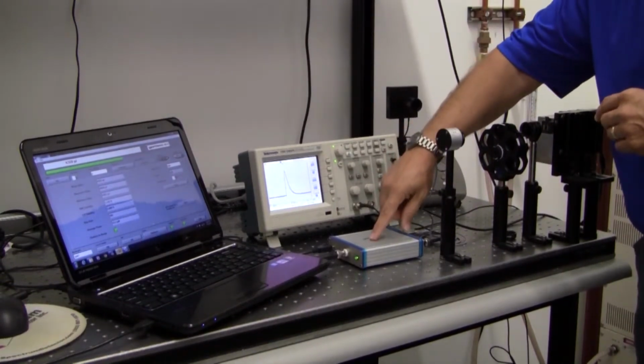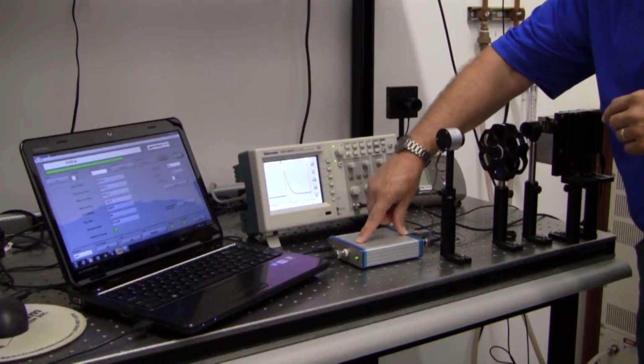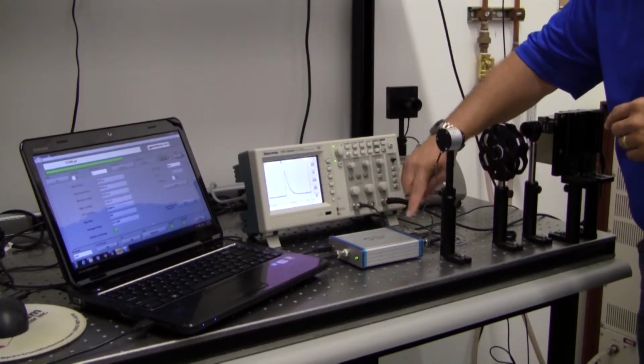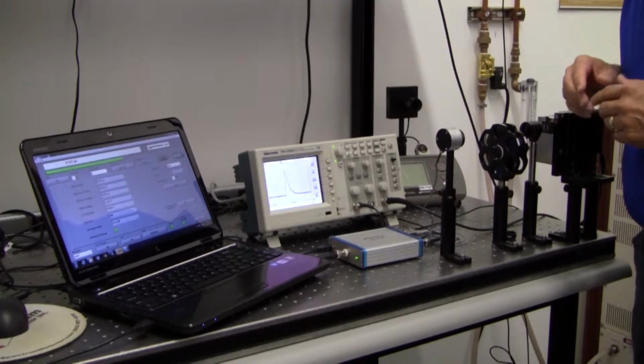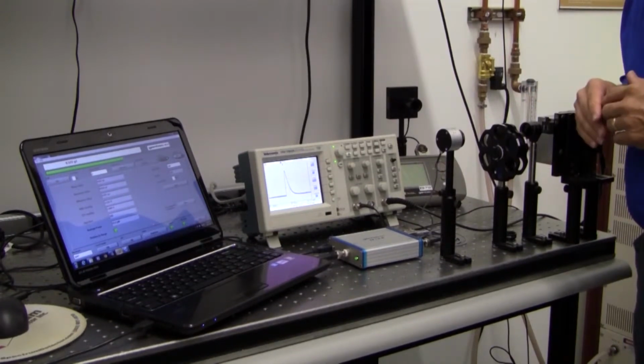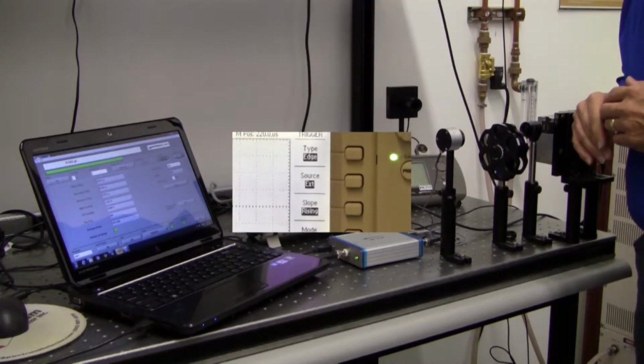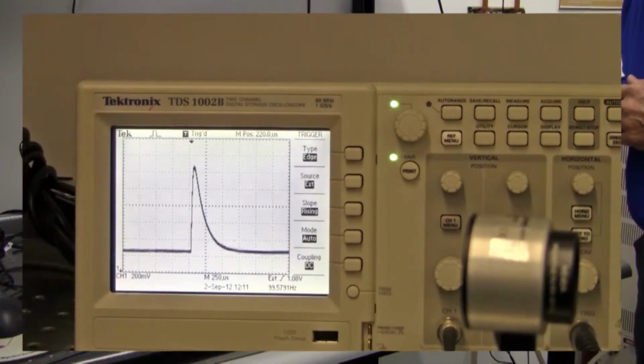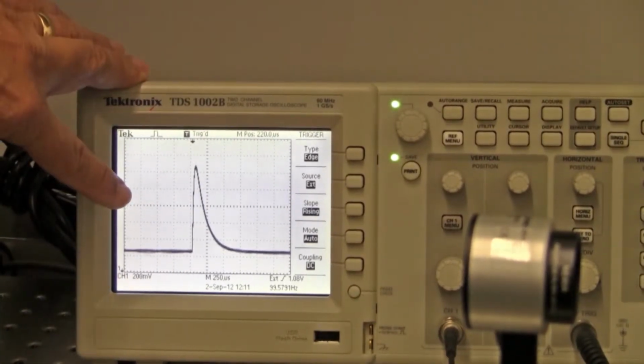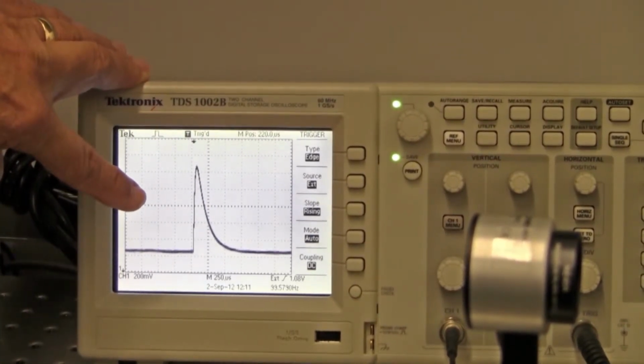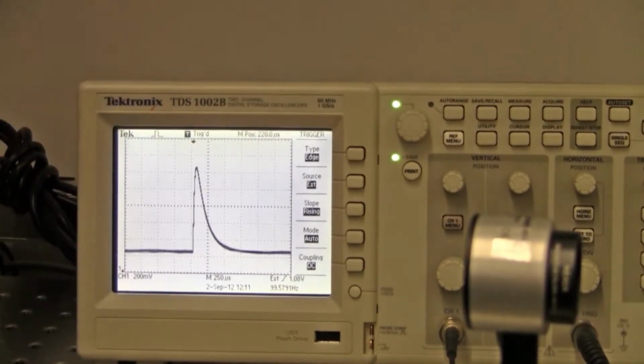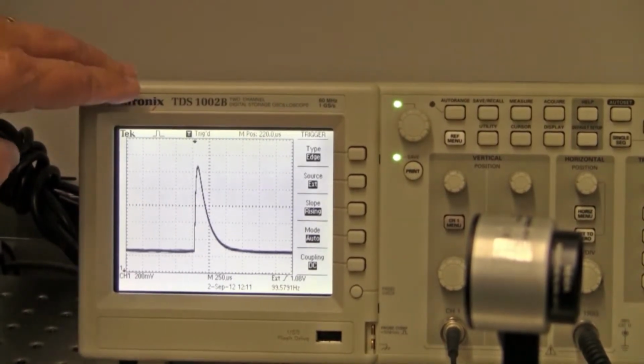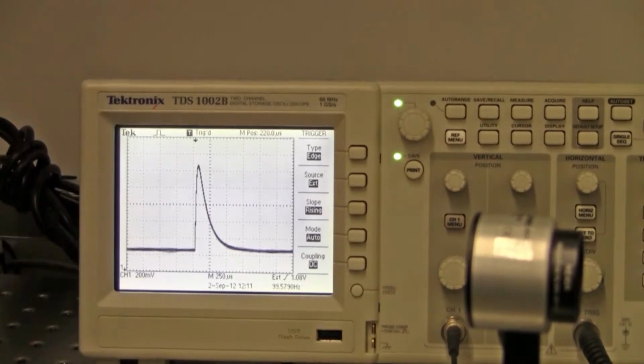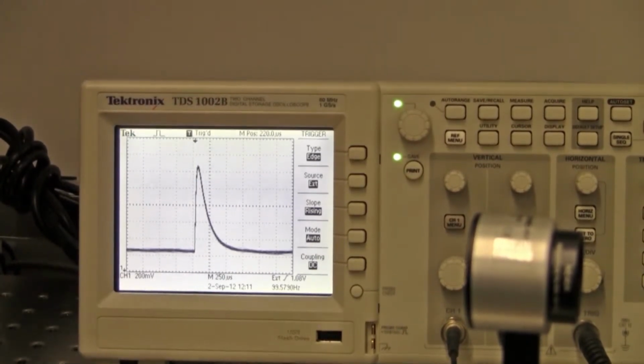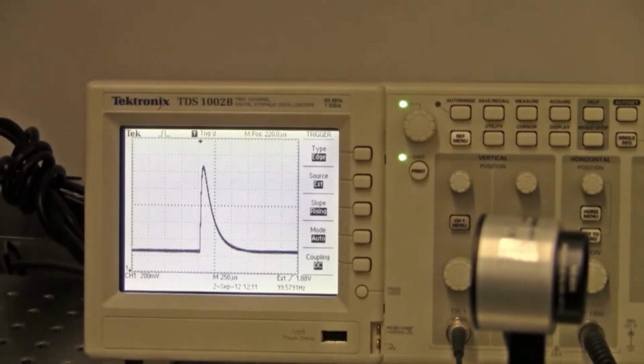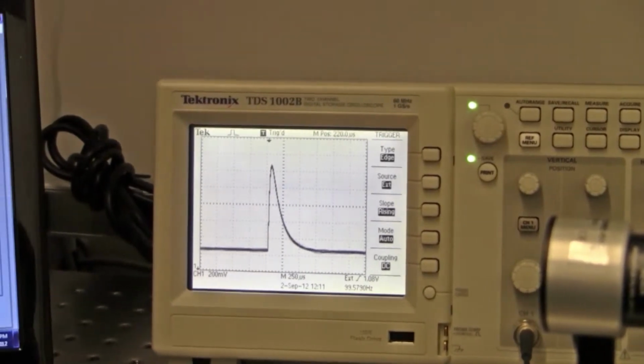We've got the laser running with it attenuated right now at about 500 femtojoules. The M-Link is set up with an external trigger from the laser and an analog output to the scope. Let's take a closer look at the probe output on the oscilloscope. So you can see on the oscilloscope we've got a very clean voltage output from the probe at about 1 volt, very stable. Obviously at 500 femtojoules this is going to be an easy thing to measure. Let's look at the software now.